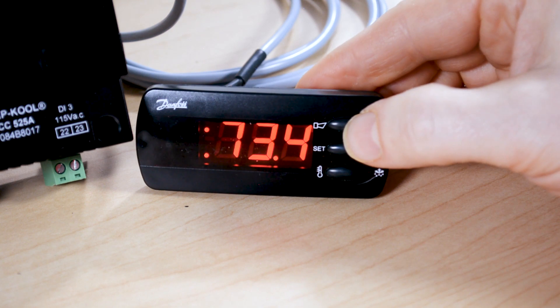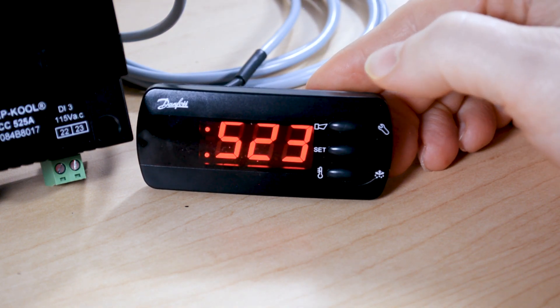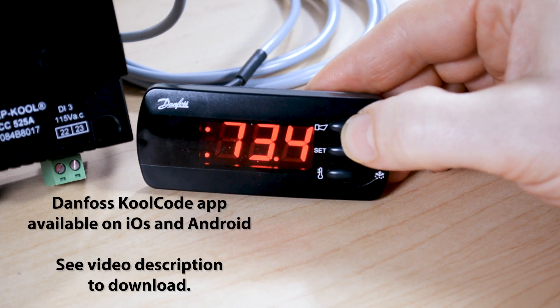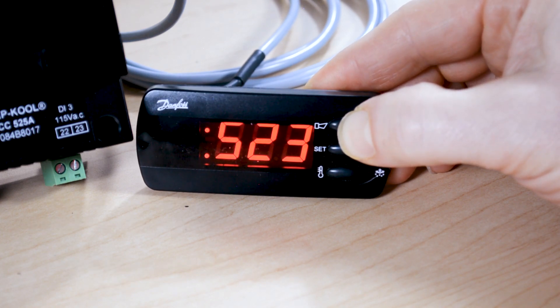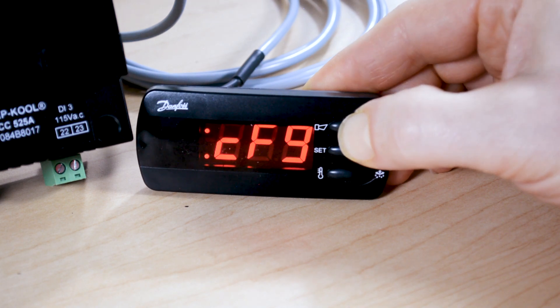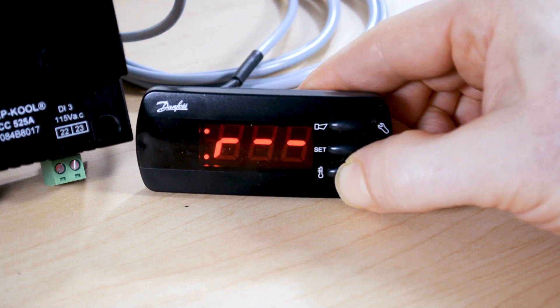The top button will give us status indications — for instance right now we're getting a status code of S23. We can look that up in our manual or on the KoolCode app to find out what it's telling us, and if we hold it again we can get alarm indications if there are any. This controller has no alarms currently, so holding it a little longer takes us into the parameter settings. From there we can get into the config menu and go into the inlet settings, outlet settings, or the R parameters.